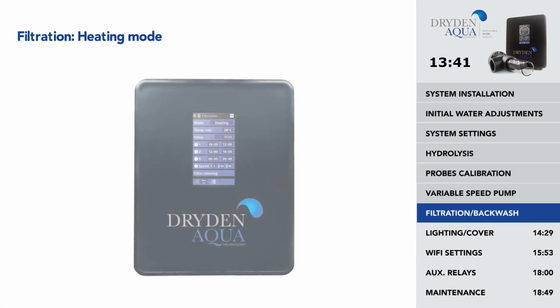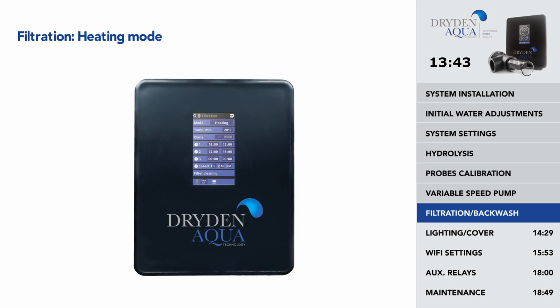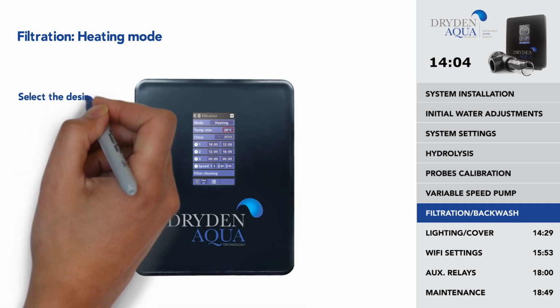Heating mode. The heating mode works the same way as the automatic mode, but also offers the option to work on a relay to control the temperature. The system works with a hysteresis of 1 degree. For example, if the temperature is set on 23 degrees, the system will activate itself when the temperature goes below 22 degrees and will not stop before it reaches 23 degrees again.